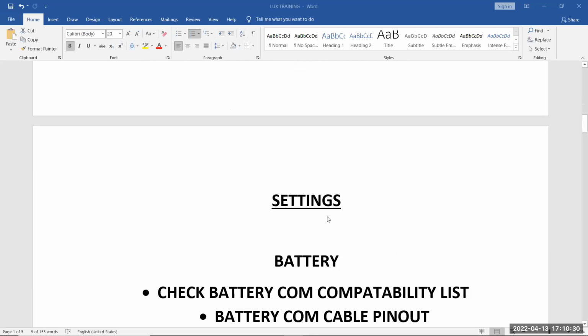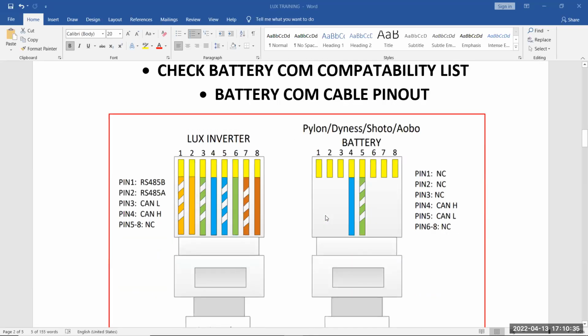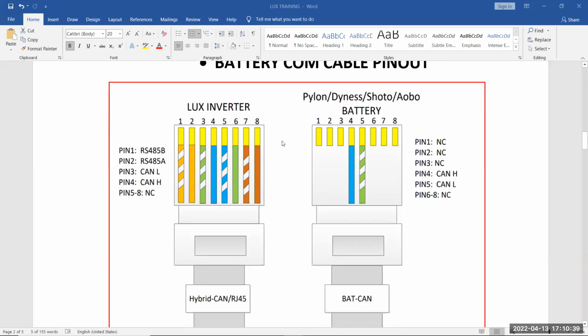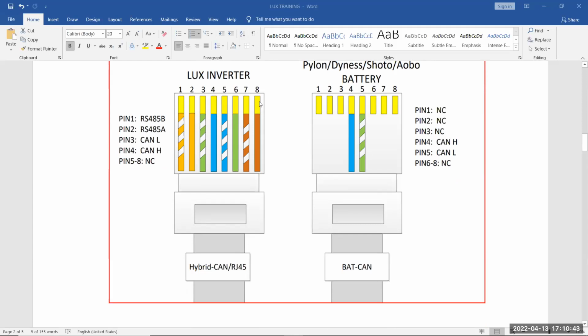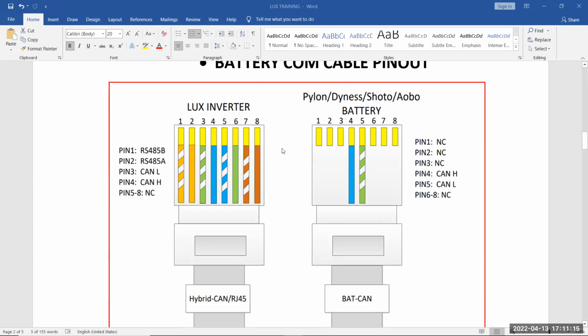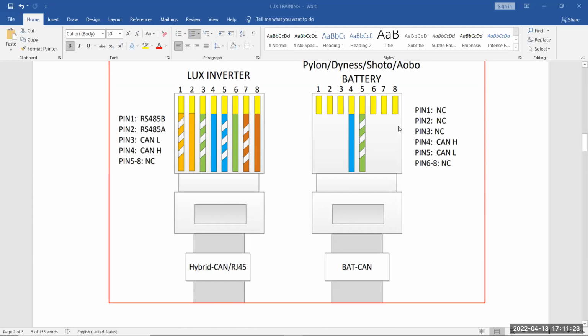So that's basically my DC side. Now, battery communication is one thing that we have a lot of problems with. You'll see my inverter cable from the inverter to the battery is a crossover cable. My number 3 on the inverter goes to number 5 on the battery, and 4 stays on 4. Please make up these cables. Most of our providers that are buying from us and supplying this inverter are starting to supply these as pre-made cables. When you buy the Luxpower unit, you'll see 4 stays on 4 and number 3 jumps to number 5. You can make this cable yourself as well if you'd like. But this is the battery cable for most of your protocols on your battery. That's your Pylon, your Dyness, your Shoto batteries, all of those batteries. 90% of them use this specific cable layout for your CAN H and CAN L port.